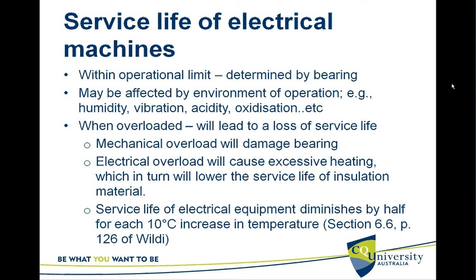The service life of electrical machines, if the machine operates within the operational limits, then the service life is determined by the bearings. If we do not exceed the operational limits in terms of voltage, current, torque, etc., which means if we operate within those limits, then the first thing to fail will be the bearings, which is a mechanical failure.